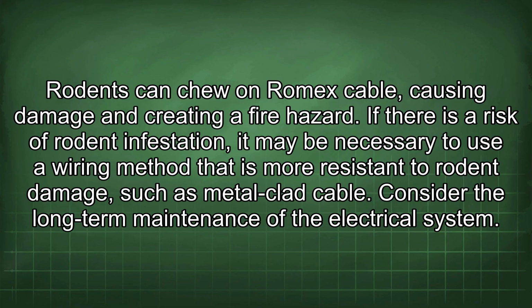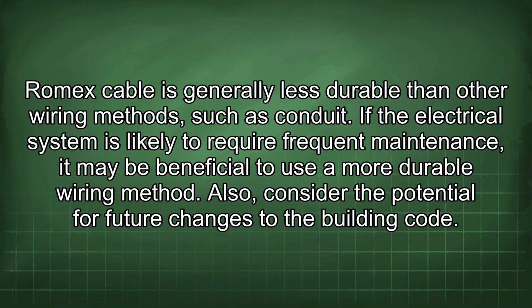If there is a risk of rodent infestation, it may be necessary to use a wiring method that is more resistant to rodent damage, such as metal-clad cable. Consider the long-term maintenance of the electrical system. Romex cable is generally less durable than other wiring methods, such as conduit. If the electrical system is likely to require frequent maintenance, it may be beneficial to use a more durable wiring method. Also, consider the potential for future changes to the building code.